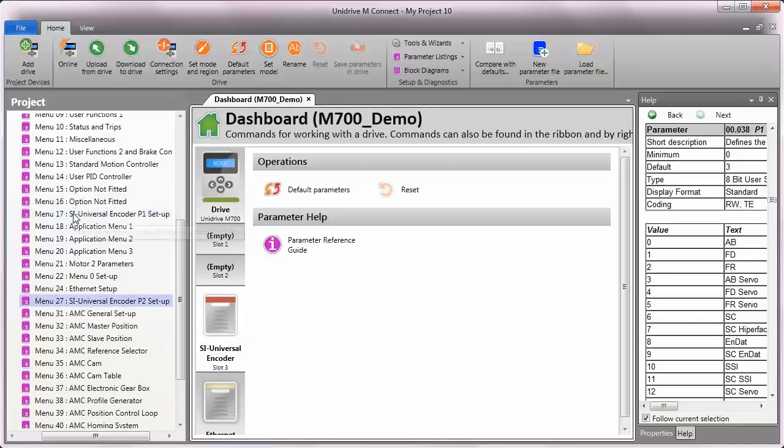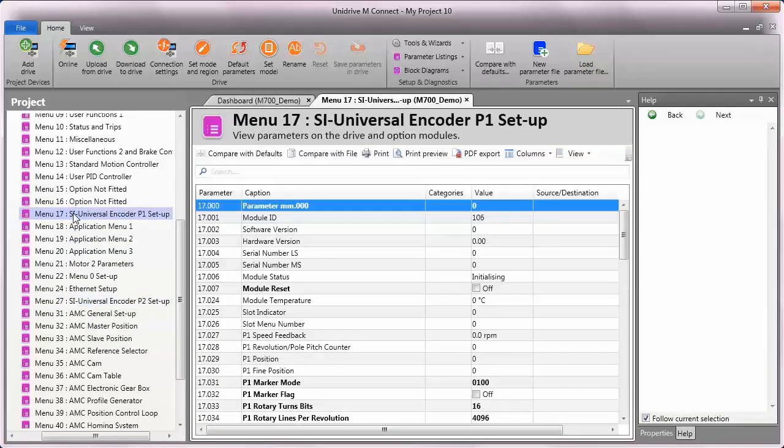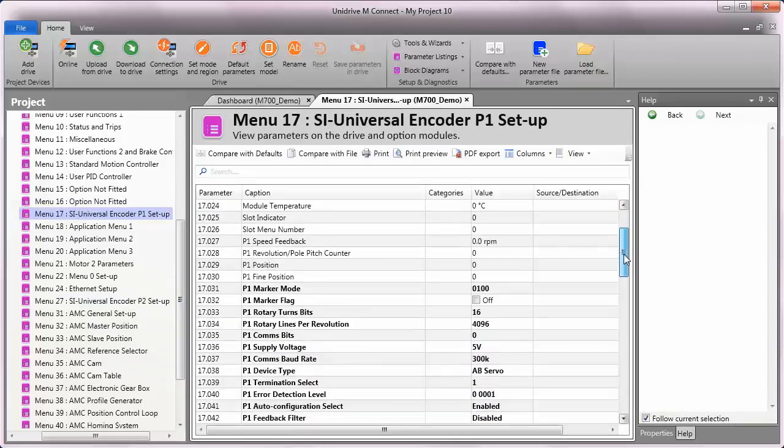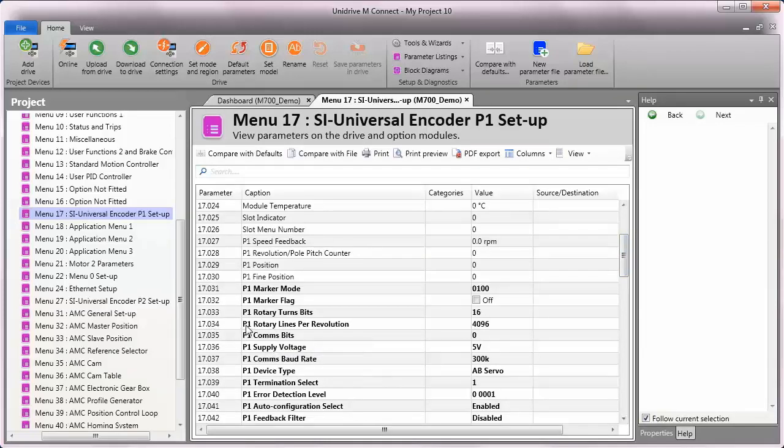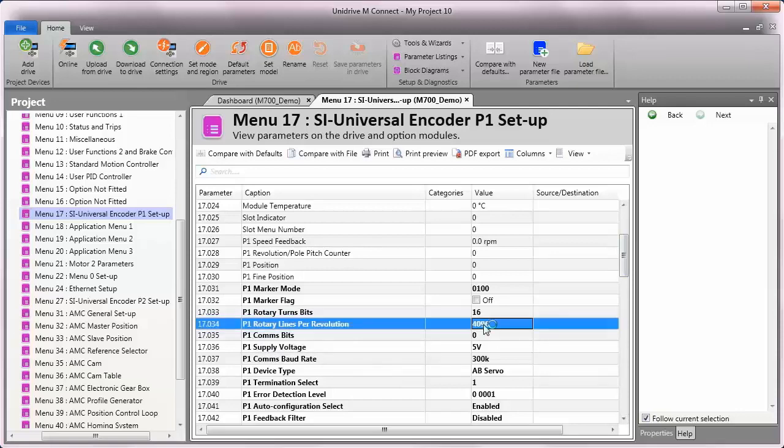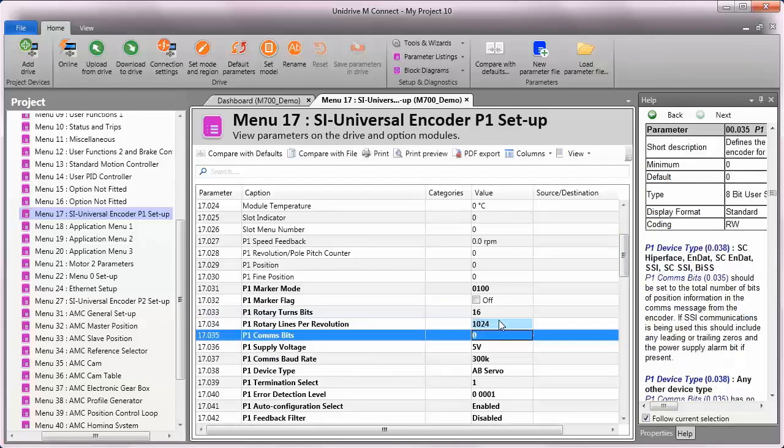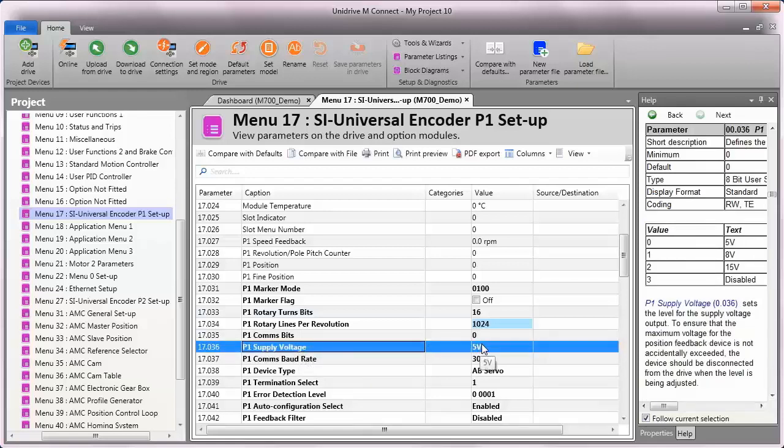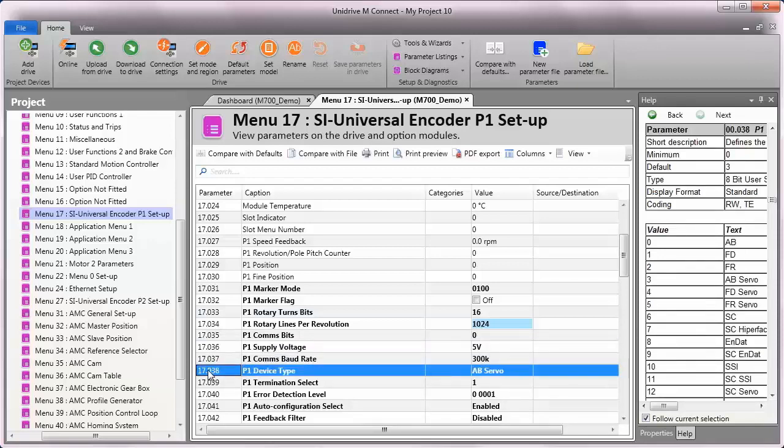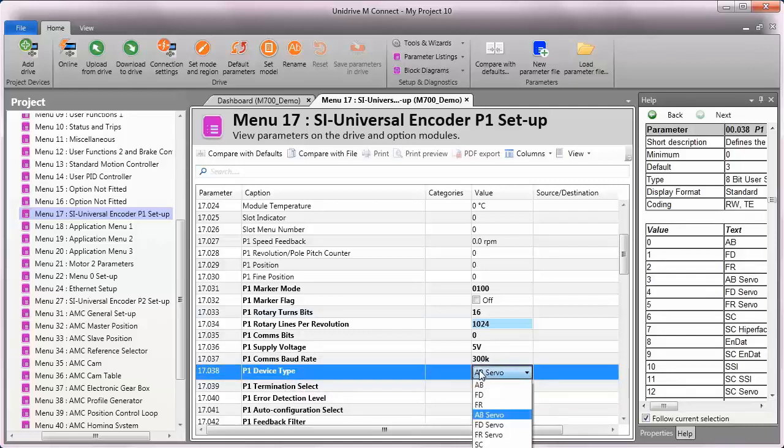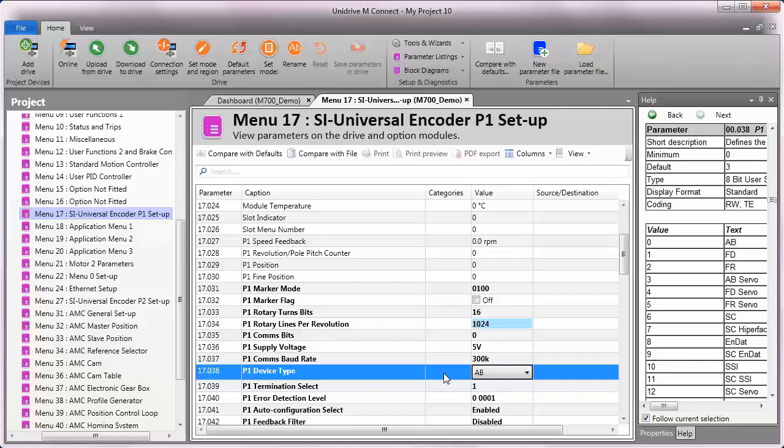So I'm going to double-click on menu 17, and we'll get the settings for the encoder that I'm using plugged in. I'm going to come down and start here with parameter 34. That is the rotary lines per revolution. My encoder is 1024 lines, so I'll plug that in here. Next, I'll check the supply voltage. My encoder is a 5-volt supply, so I don't need to change anything there. And then I'm going to come down and choose the device type itself. The encoder that I'm using is just a standard quadrature encoder. So our designation for that type of encoder is, I'll drop the list down, is just AB. So that's all I need to do at this point to configure that encoder that's on the conveyor. Now I'll move into menu 13, and we'll configure the standard motion controller.